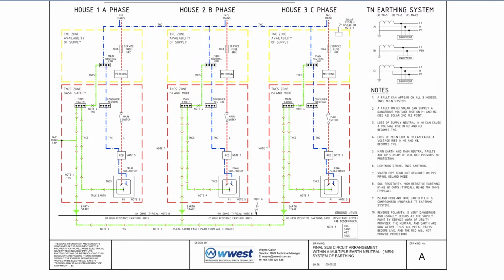We've got soil resistivity, which is high resistive earthing from H1 to H2. Now, you'd have to have at least 15 meters between this earth stake and this earth stake, just in practicality. And so I've just given it a typical value of 6,000 ohms between there and there. So between this earth stake and this earth stake, you've got a high resistive earthing. There's no low impedance earthing, or the only low impedance earthing that you've got is this line here, all the way up there like that, and then down here to your earth stake, which is typically 2 ohms.